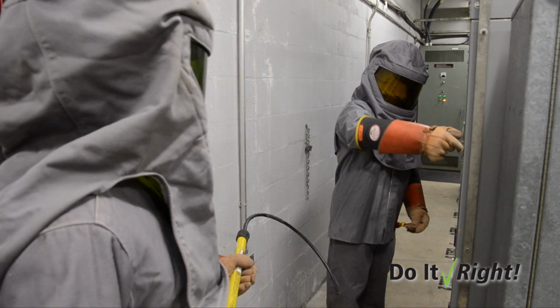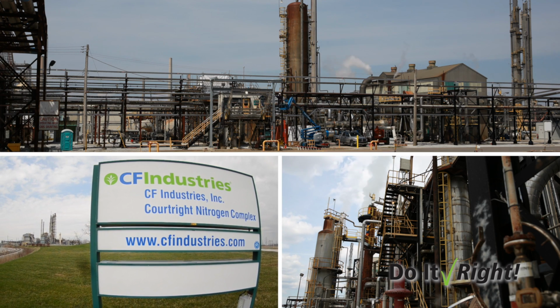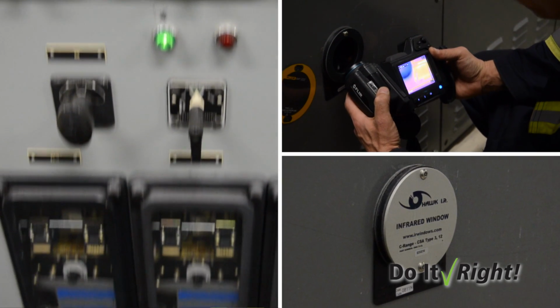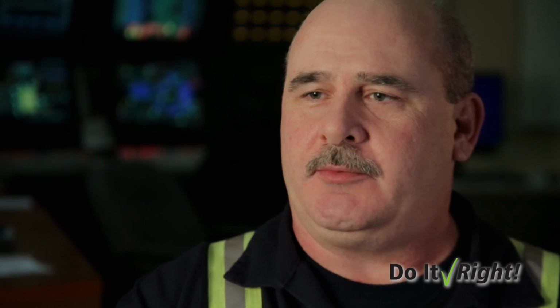The process of completing an IR scan can be very dangerous. There is a significant potential for a fatality with this activity. The site is fed by 35,000 volts, so the danger to get zapped or have a huge arc flash event is quite large. With due diligence, we've made the job as safe as possible.